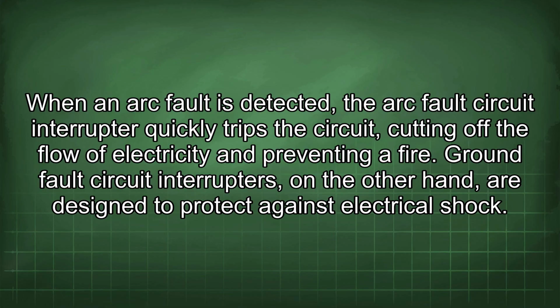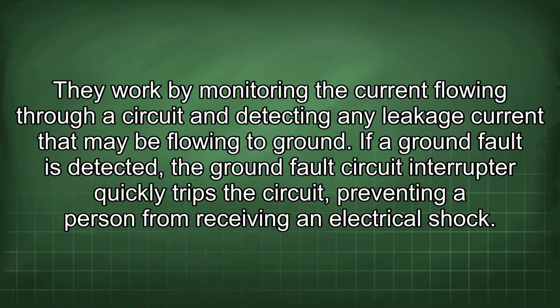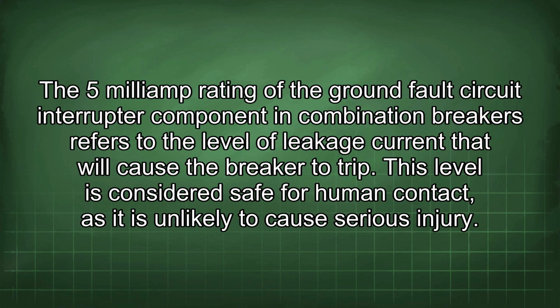Ground fault circuit interrupters, on the other hand, are designed to protect against electrical shock. They work by monitoring the current flowing through a circuit and detecting any leakage current that may be flowing to ground. If a ground fault is detected, the ground fault circuit interrupter quickly trips the circuit, preventing a person from receiving an electrical shock. The 5 milliamp rating of the ground fault circuit interrupter component in combination breakers refers to the level of leakage current that will cause the breaker to trip. This level is considered safe for human contact, as it is unlikely to cause serious injury.